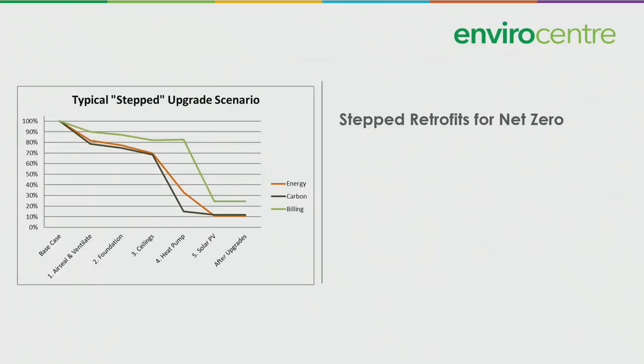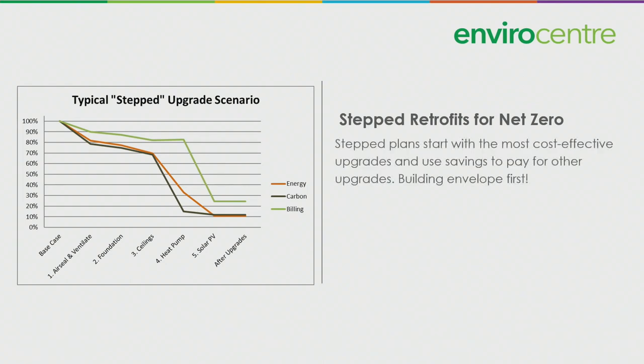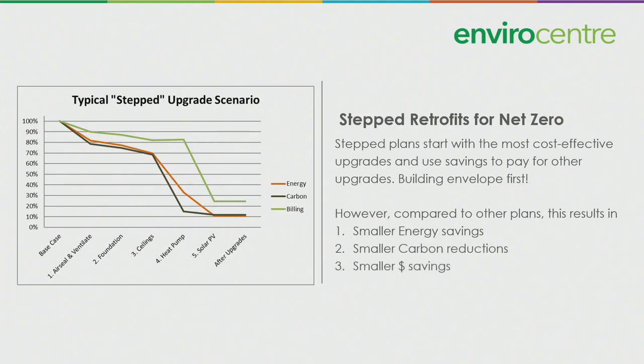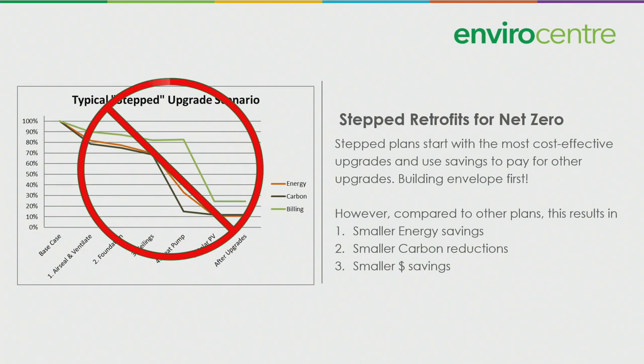Let's look at stepped retrofits for net zero. These stepped plans start with the most cost-effective upgrades and use savings to pay for other upgrades. And typically, it's building envelope upgrades first. This is a particular scenario that was performed on a heritage building in downtown Ottawa, so the upgrade scenarios are somewhat limited by what you can do to the exterior of the building. However, when you compare the stepped retrofit scenario to other plans, this results in smaller energy savings, smaller carbon reductions, and smaller dollar savings. So I don't recommend it.